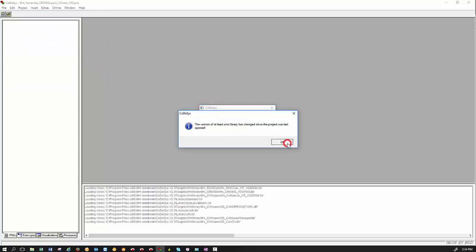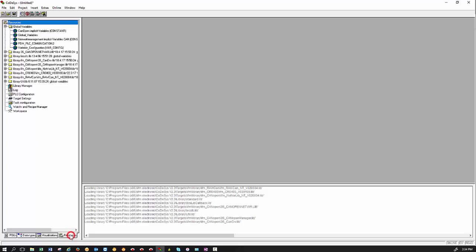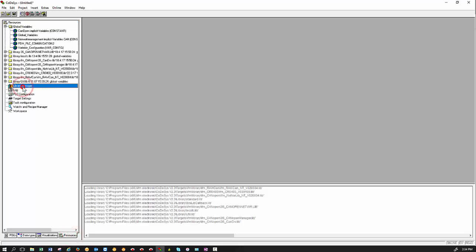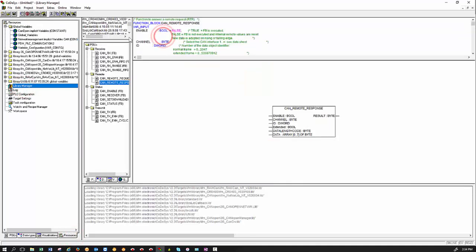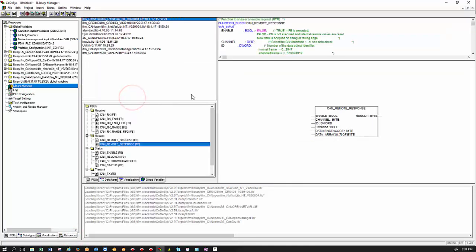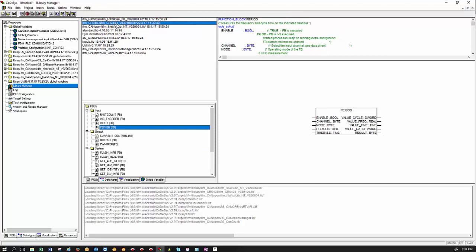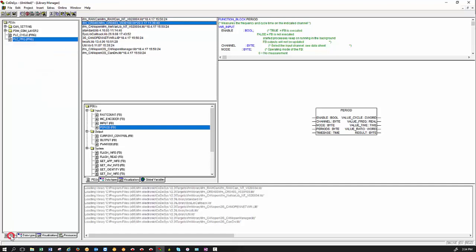The reason we use the template is because it has all the libraries required by the basic controller already in there. So if you go to Resources and Library Manager, double-click on Library Manager, you will see that we have all the necessary libraries required. And there is one of the most important libraries which we call the CR0403 Device Library. And in there we have all the function blocks required to configure inputs and outputs. So today we will be covering some very basic inputs and outputs like a digital input and an analog input. And in the outputs we will be covering a digital output and PWM outputs.